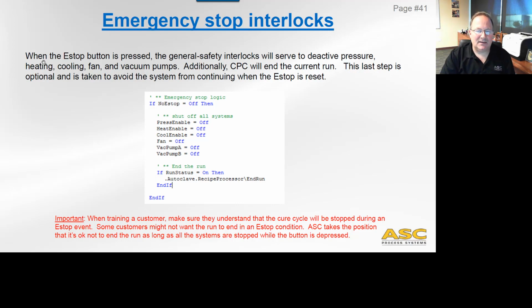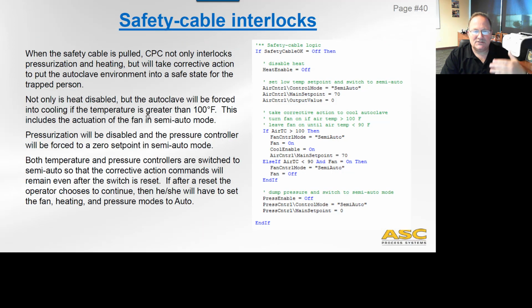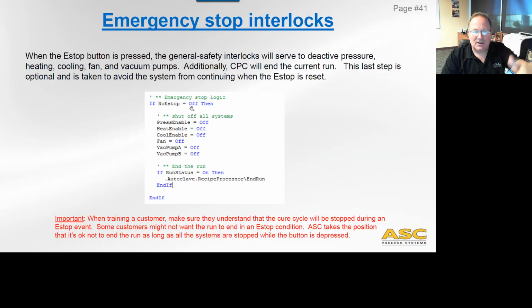Emergency stop interlock. Again, this is in the order that we're going to see it in the general safety. So this is the very last thing we're going to see in our general safety scripting. When the e-stop is pushed, the general safety alarm will deactivate pressure, heating, cooling, fan, and vacuum pumps. Additionally, CPC will end the current run. So this is an important part that is usually missing from our logic, and it says, hey, if I hit e-stop, I want the run over, okay?